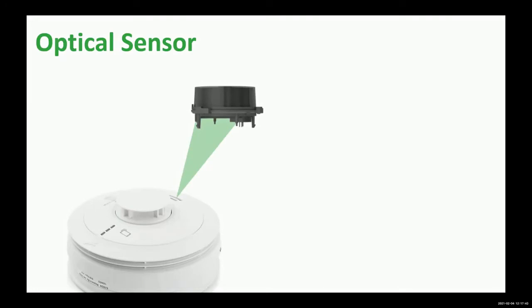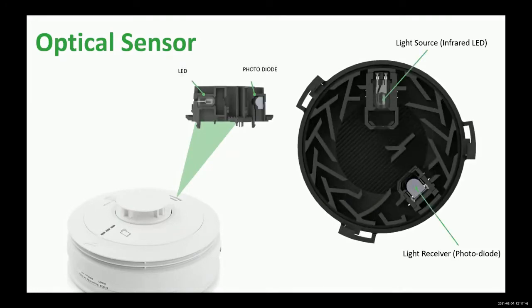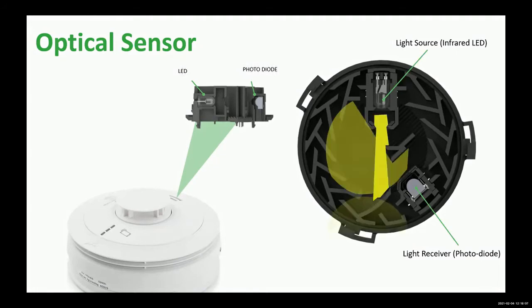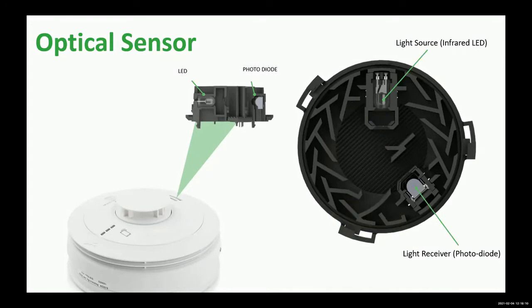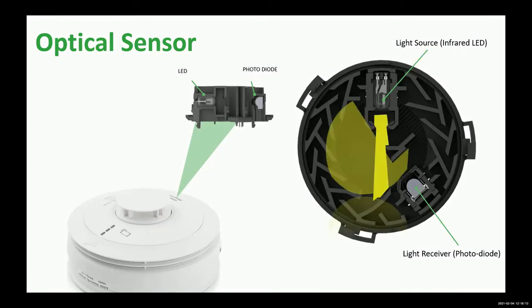So if we just look at the sensor itself and how it operates, what you have on the top of the unit is a light source, an infrared LED, and that pulses a beam of light into the chamber every 10 seconds. At the bottom right-hand corner, on the southeast, you can see the light receiver is a photodiode, and that's, I suppose, shaded and kept away from the light source in normal circumstances. If we just look here at the pulse being sent out, those yellow sections represent where the light will transmit around the chamber itself. You can see the light receiver hasn't been hit in that area yet because it's protected by baffles within the chamber. So we're just looking at reflective sources at this stage.